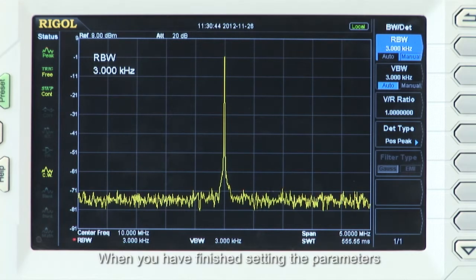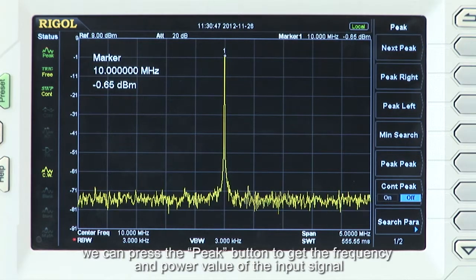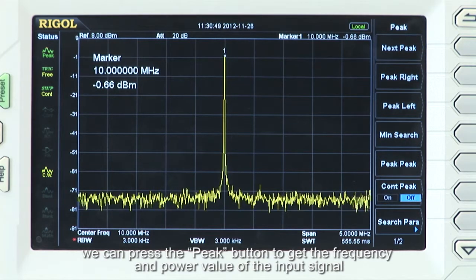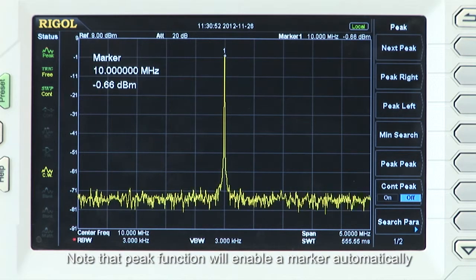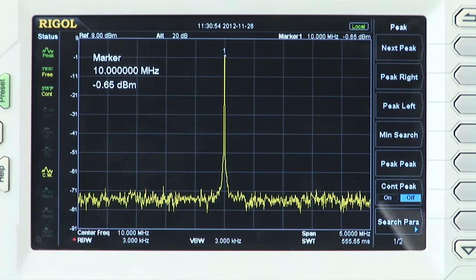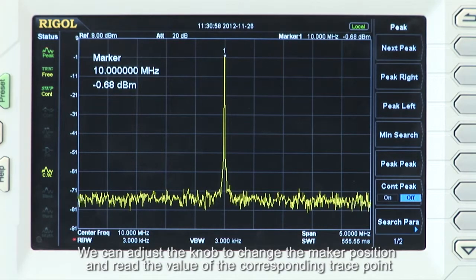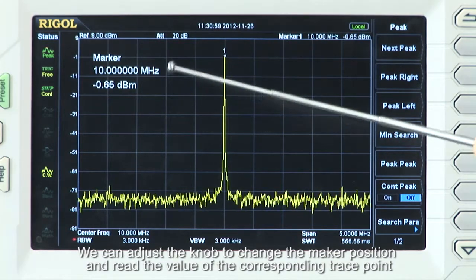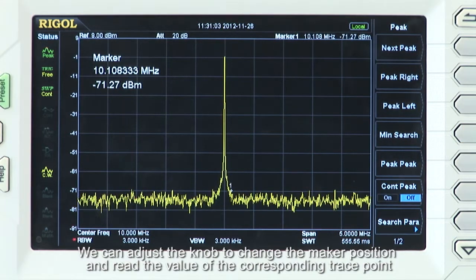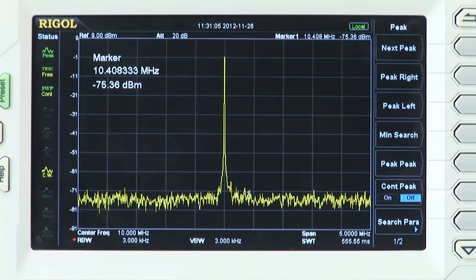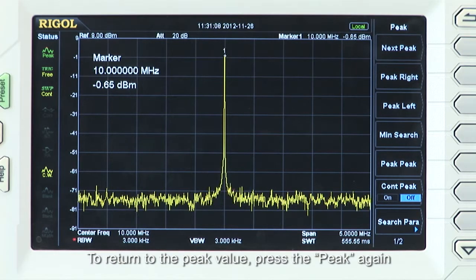When you have finished setting the parameters, you can also use the peak button to get the frequency and power value of the input signal. Note that the peak function will enable a marker automatically and point out the maximum value on the trace. You can use the adjustment knob to change the marker position and read the value of the corresponding trace point. To return to the peak value, you can press peak again.